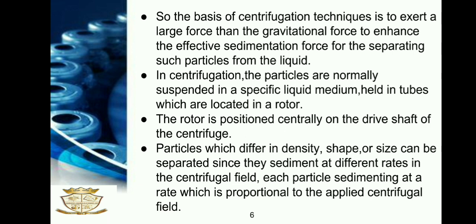In centrifugation, the particles are normally suspended in a specific liquid medium held in tubes located in a rotor. In a solution, particles whose mass or density is higher than that of the solvent sink or sediment, and particles that are lighter than it float to the top. The greater the difference in mass or density, the faster they sink. The rotor is positioned centrally on the drive shaft of the centrifuge. Particles which differ in density, shape or size can be separated since they sediment at different rates in the centrifugal field, each particle sedimenting at a rate proportional to the applied centrifugal field.